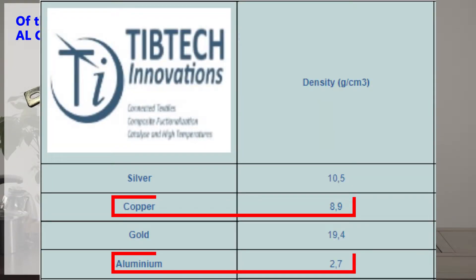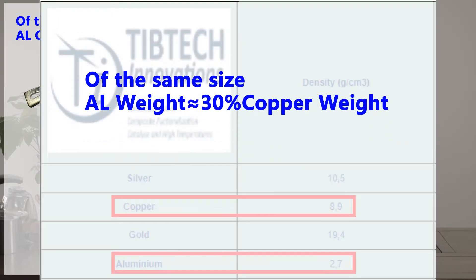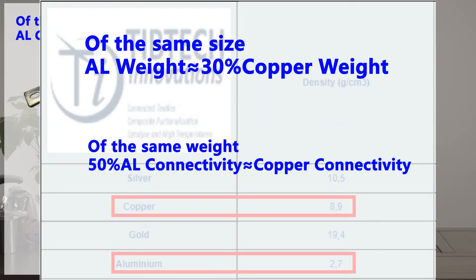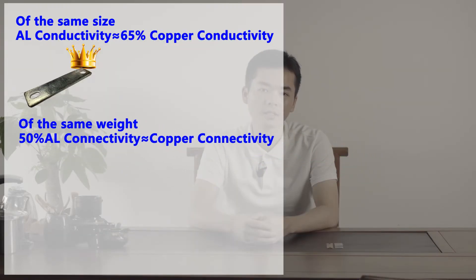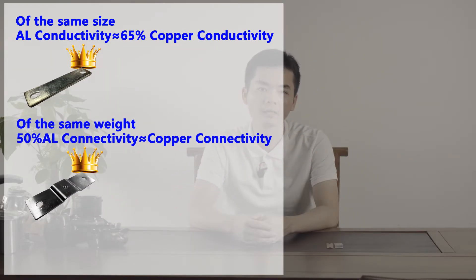On the other hand, aluminum material is 70% lighter than copper material. So when you compare conductivity by weight, you will find that aluminum material is actually 50% more conductive than copper material. So in this case, aluminum material gets the upper hand. The second point is price and cost.